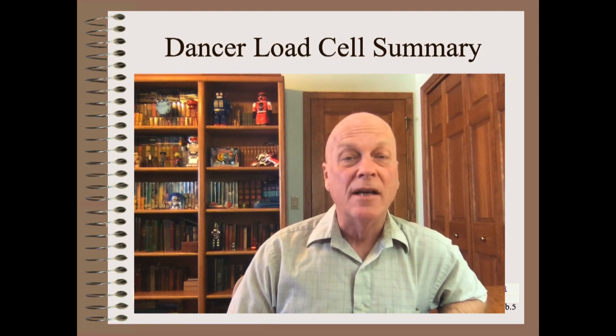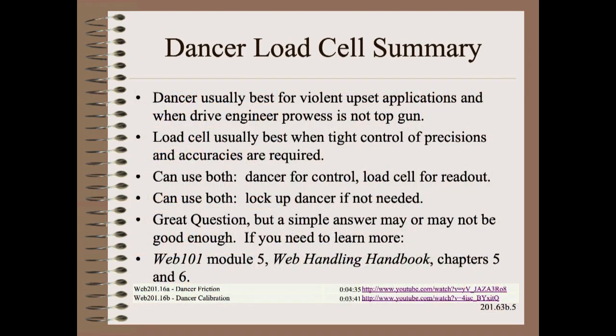Dancers and load cells each have their own strengths and weaknesses. However, if you are a designer or buying a new machine, you might wish to incorporate both in a single drive section. This gives you the widest possible control possibilities. For example, you could use the dancer for control and the load cell for a readout of tension control quality and to check against the dancer, which also should be calibrated in tension units. If you find the dancer unnecessary or even unhelpful, you can simply lock it out for movement and use the load cell output as feedback to the drive motor.